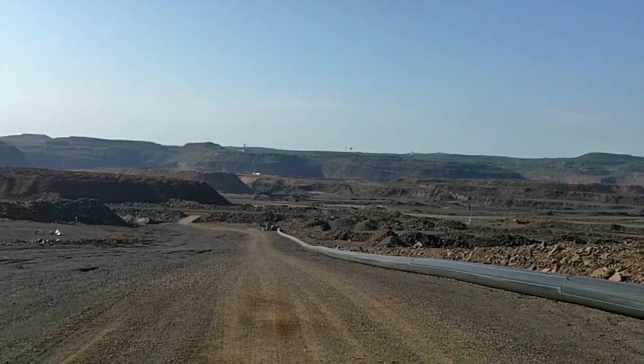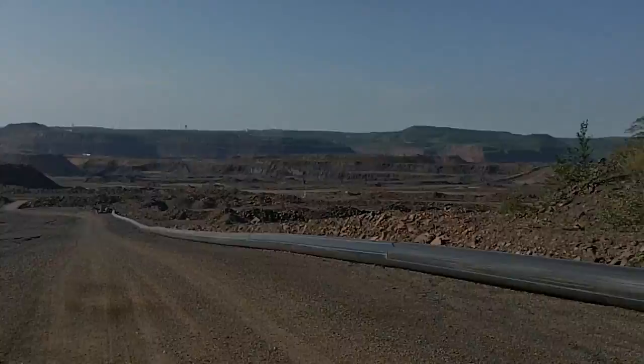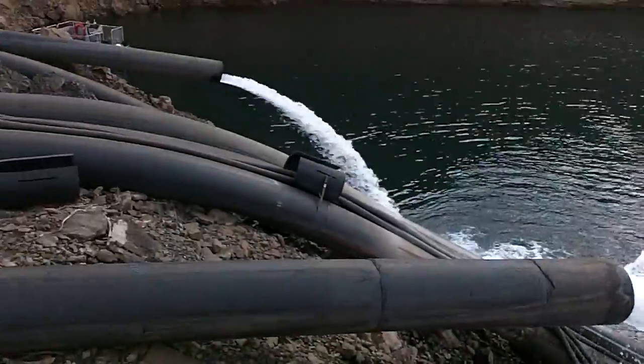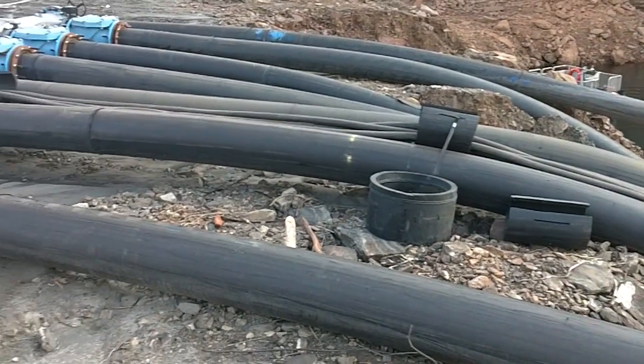Additionally, the water transfer would need to overcome 400 feet of head across more than two miles to reach the mine's production supply reservoir. These floating pumps fed 12-inch HDPE pipelines into one common valve manifold and into two steel tanks for holding.